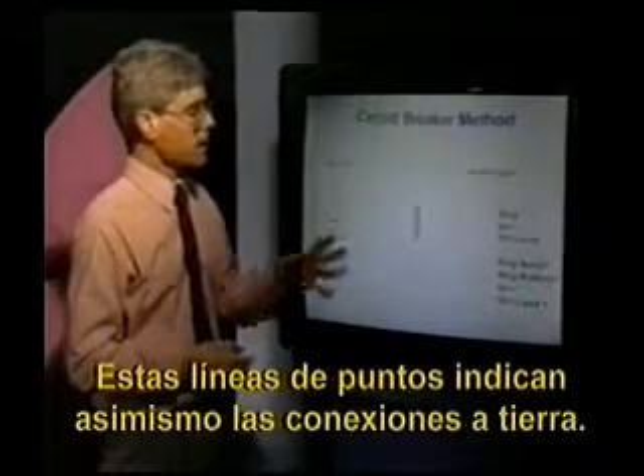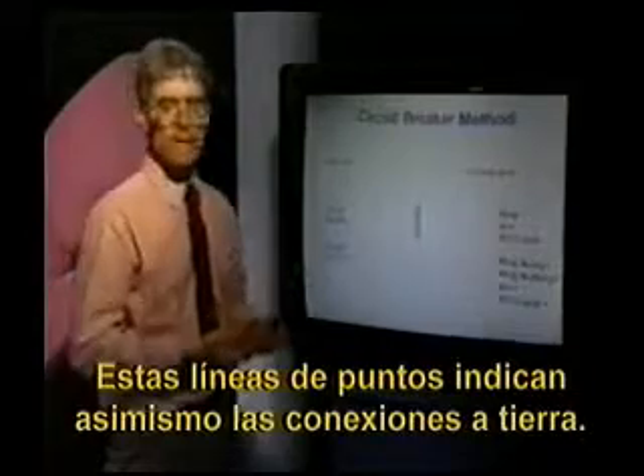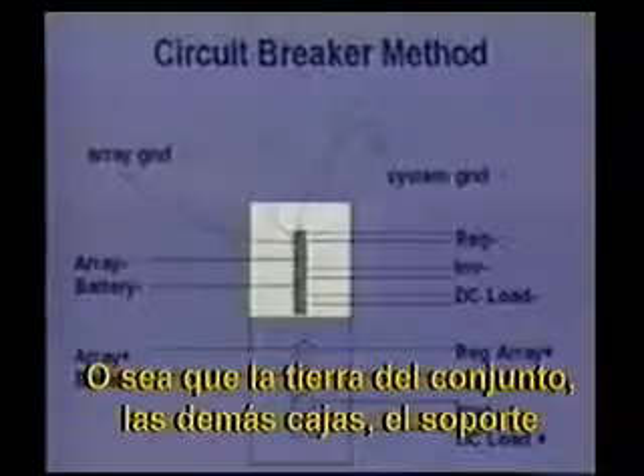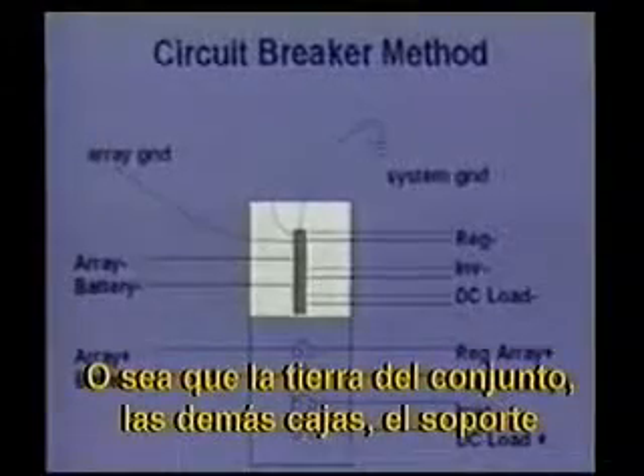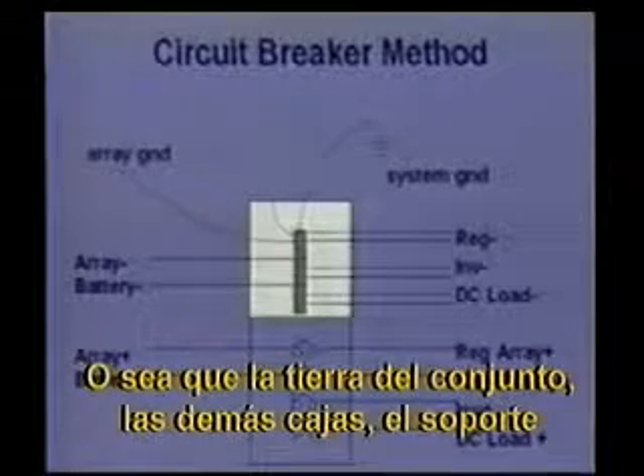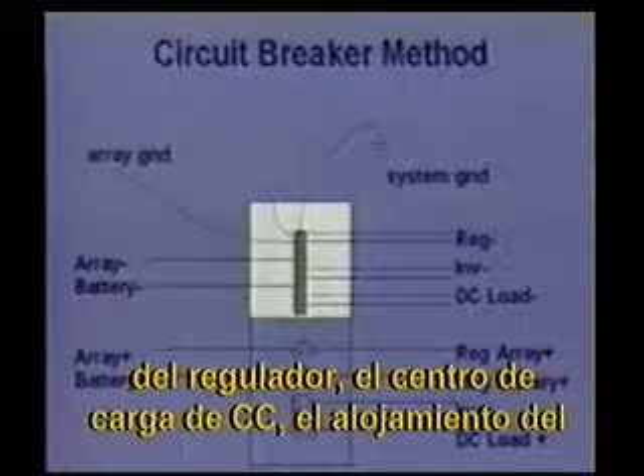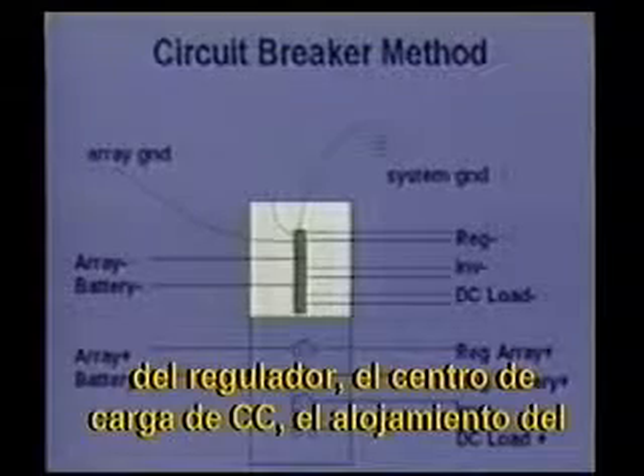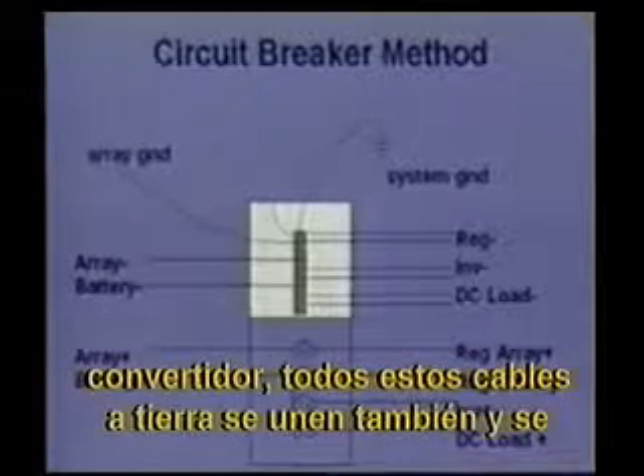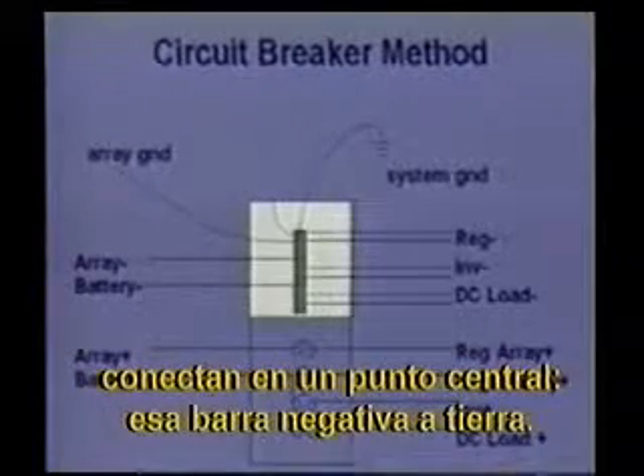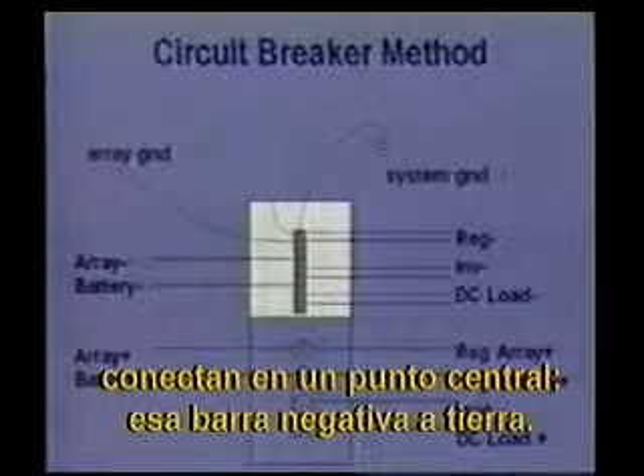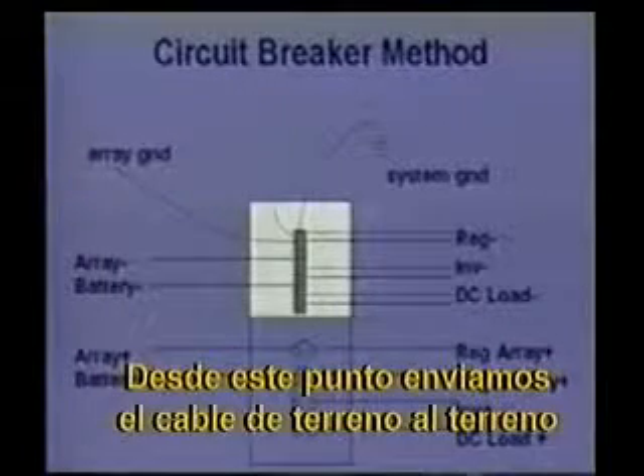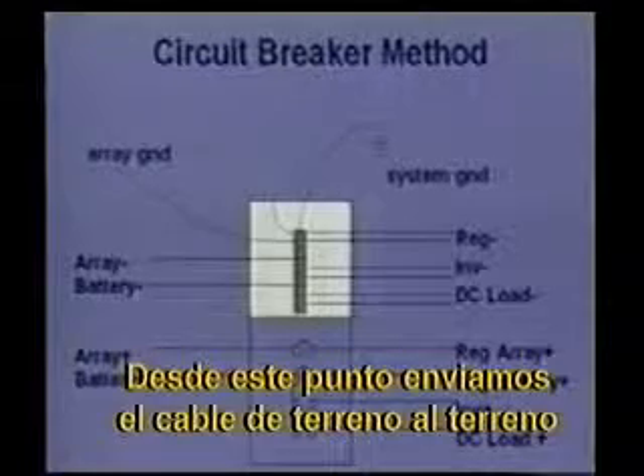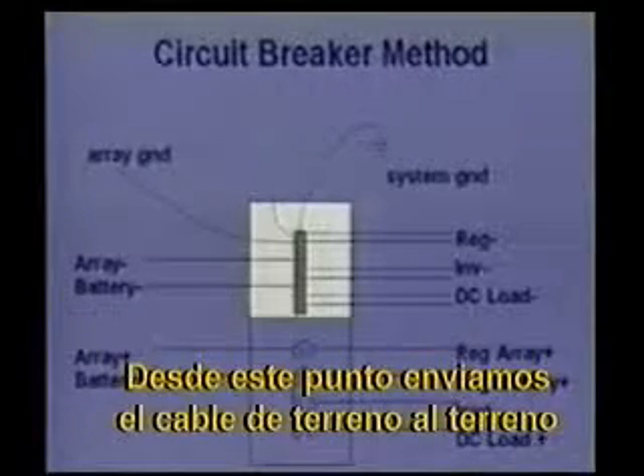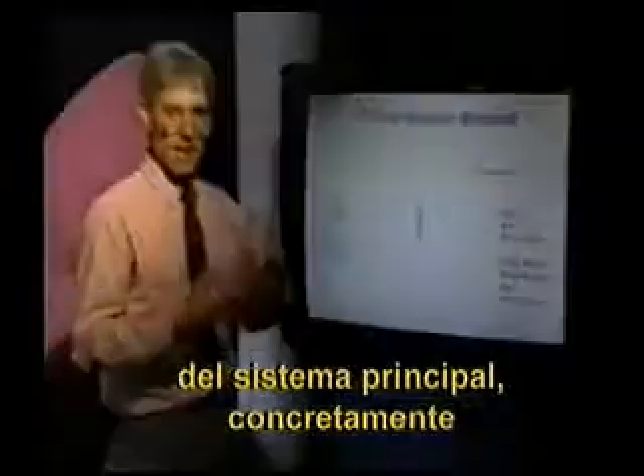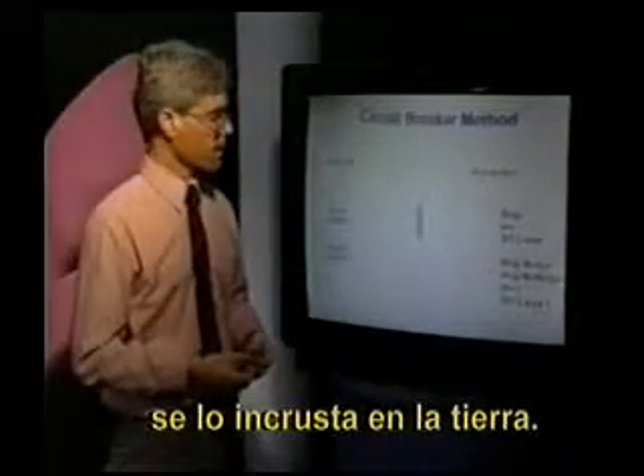The small dotted lines that I've included indicate the grounding connections as well. So the array ground, your other boxes that might be involved with holding the regulator, the DC load center, the inverter housing, all of these ground wires come together as well and are all connected at one central point, that negative grounding bar. It's from this point that we send our grounding wire out to our main system ground. It's actually put into the earth.